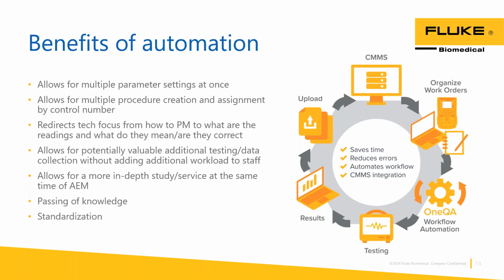It allows for multiple procedure creation and assignment by control number. So what this means is that we can track the actual test by the control number, and also create the procedure and work orders, multiple of them at a time, allowing for time save, which redirects the tech focus from how to PM to what are the readings, what do they mean, and are they correct. So with this, the automation is allowing us to not necessarily focus on pressing the buttons on the device, but making sure that the values are correct on the monitor. Hey, can I jump in there for one second?